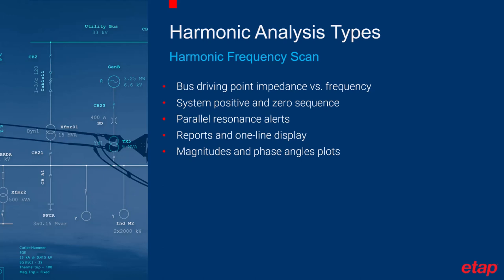The ETAP frequency scan program is the tool to investigate the system resonance problem. It calculates and plots the magnitudes and phase angles of bus driving point impedance over a frequency range specified by the user. Thus, any parallel resonance condition and its resonance frequency can be clearly identified. The harmonic frequency scan study also allows users to tune their harmonic filter parameters and test the final results.